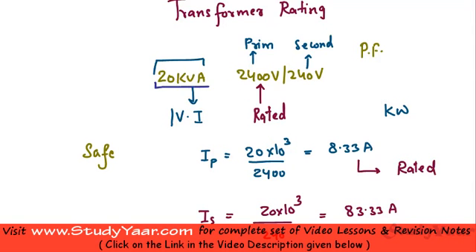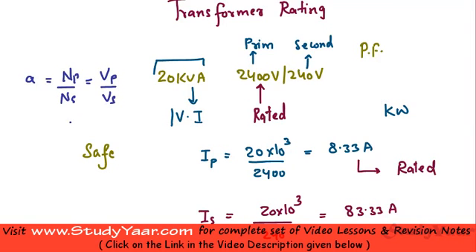When you are given a transformer rating, you are also given your turns ratio. The turns ratio is simply the number of turns in primary divided by number of turns in secondary, which is equal to voltage in primary divided by voltage in secondary. In this case, the maximum voltage in primary is 2400 and the maximum voltage in secondary is 240, therefore your turns ratio 'a' is basically 10.